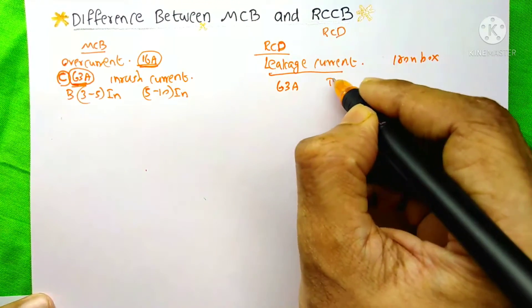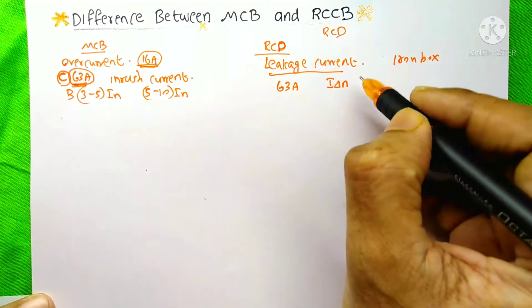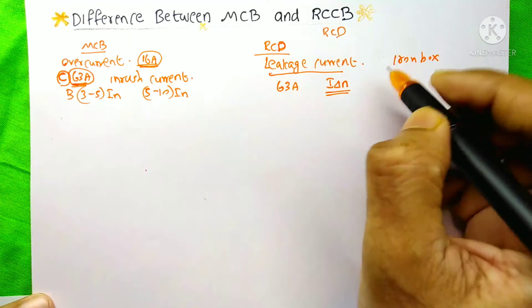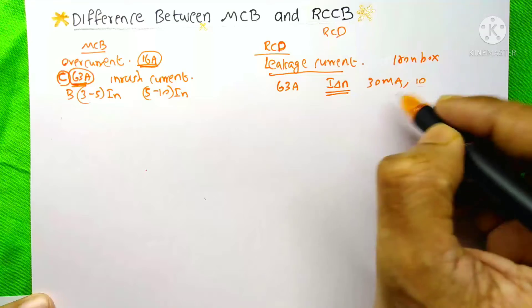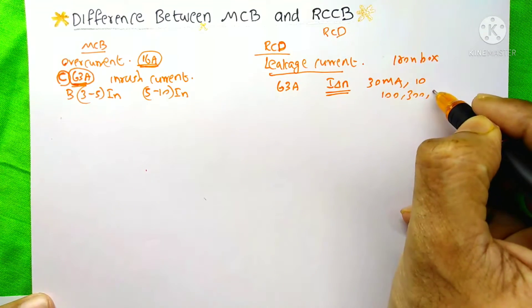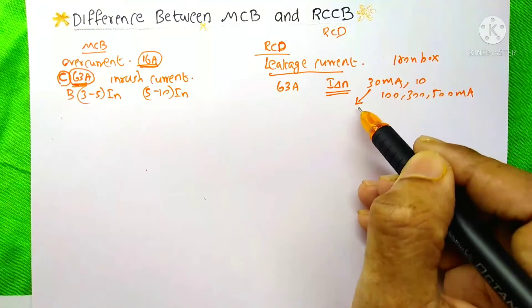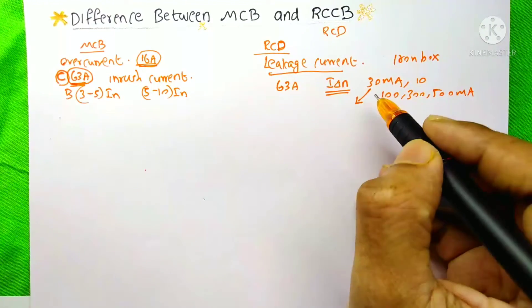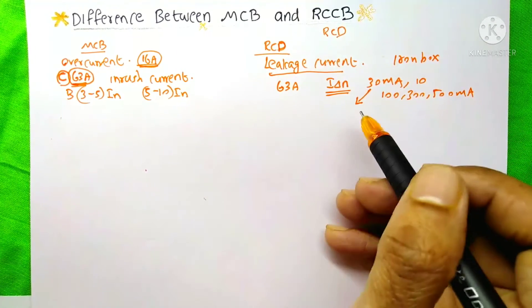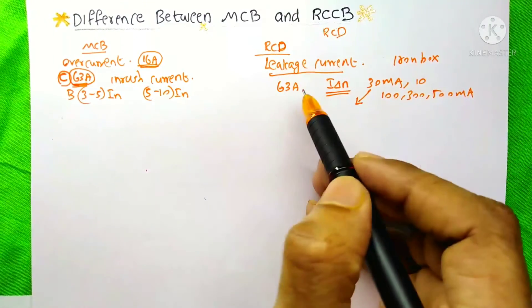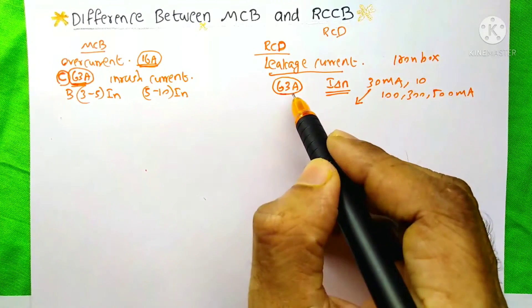But here in the RCD, you can see an extra thing that is this I delta N. This I delta N has 30 mA or 10 mA, 100 mA, 300 mA, 500 mA. Suppose our RCD is for this 30 mA, then if our circuit's leakage current is more than this 30 mA, then the RCD will trip and protect us. And here for the RCD, only up to 63 ampere current is available in the market.